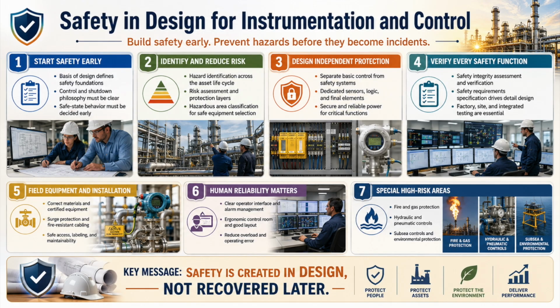The control and shutdown philosophies must then explain how operators interact with the plant, how alarms are prioritized, how abnormal situations are handled, and how the facility moves to a safe state. These documents are not administrative paperwork. They are the contract between process intent, control logic, operator action, and protective response. Functional logic must be visible, testable, and understandable by someone other than the original designer. Cause and effect relationships, trip actions, permissives, overrides, resets, and safe state behavior must be documented clearly enough for another engineer to configure, review, test, and maintain the system without guessing.